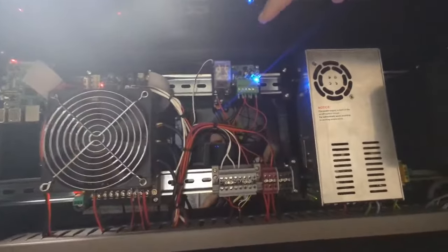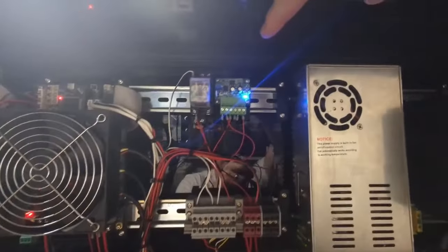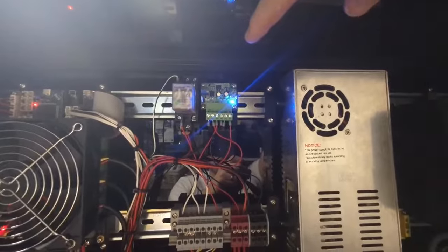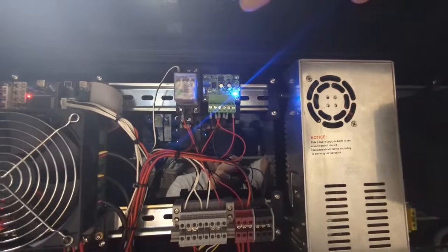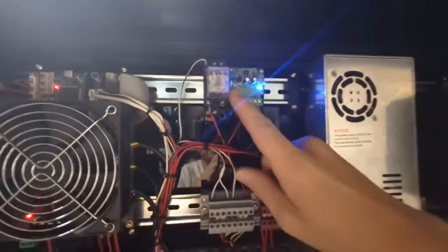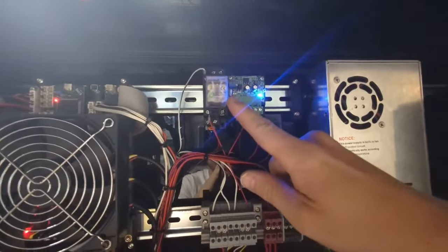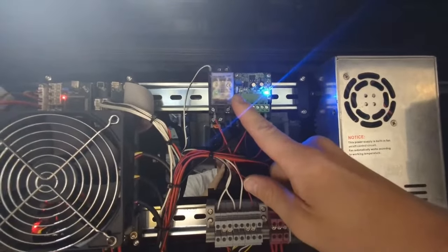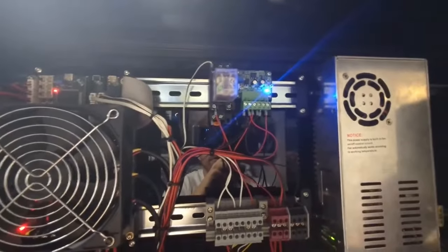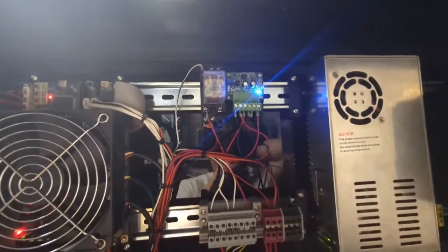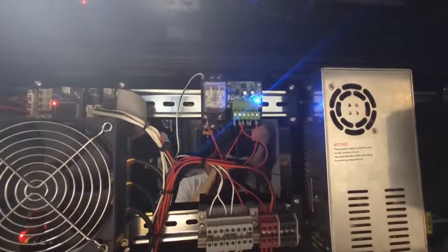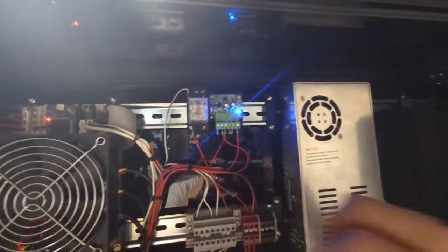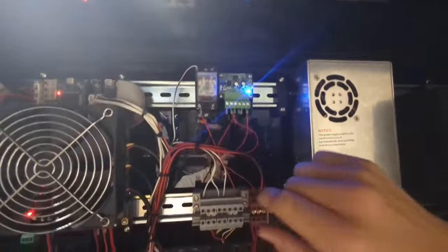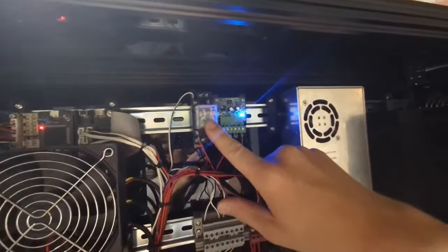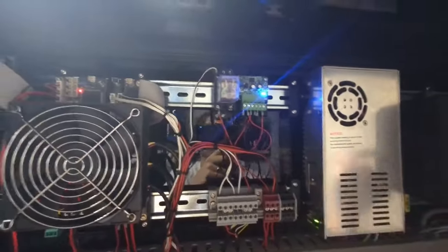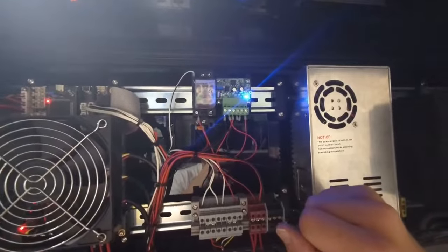I've got a relay and a 0 to 10 volt board up here, which we use to interface with the VFD. The VFD expects the forward input to be connected to ground on the VFD - you can't just connect it to a sinking input pin, it doesn't work very reliably doing that. So instead we switch a relay on or off, and that closes the contact for us.